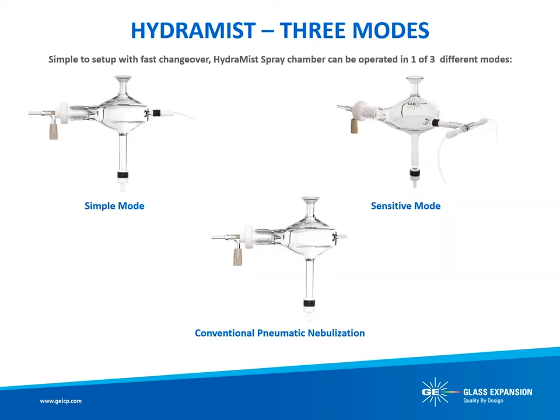The HydraMist spray chamber can be operated in one of three different modes. The simple mode provides simultaneous hydride and pneumatic nebulization with a five-fold improvement in detection limits for hydride-forming elements while maintaining analytical performance for non-hydride elements. With the addition of an extra sample input and T-piece, the HydraMist provides a sensitive simultaneous cold vapor and pneumatic nebulization mode with more than ten-fold improvements in detection limits for cold vapor elements without compromising performance of non-hydride-forming elements. Finally, it can be used as a conventional cyclonic spray chamber with pneumatic nebulization.